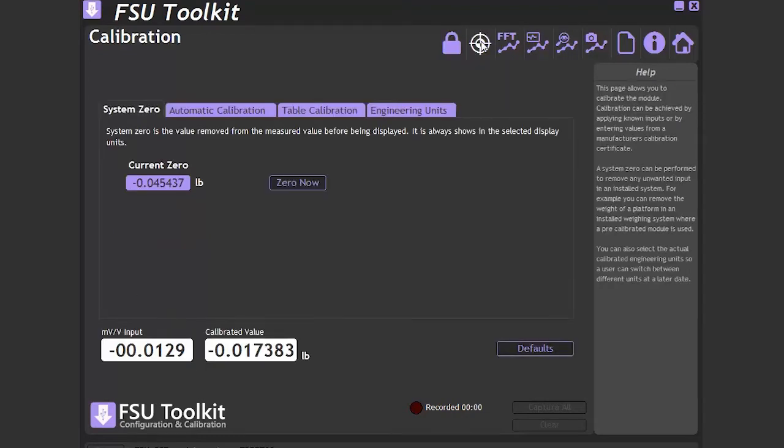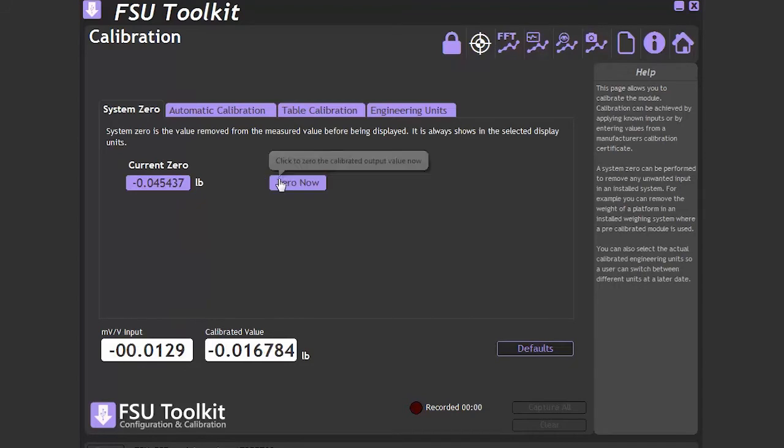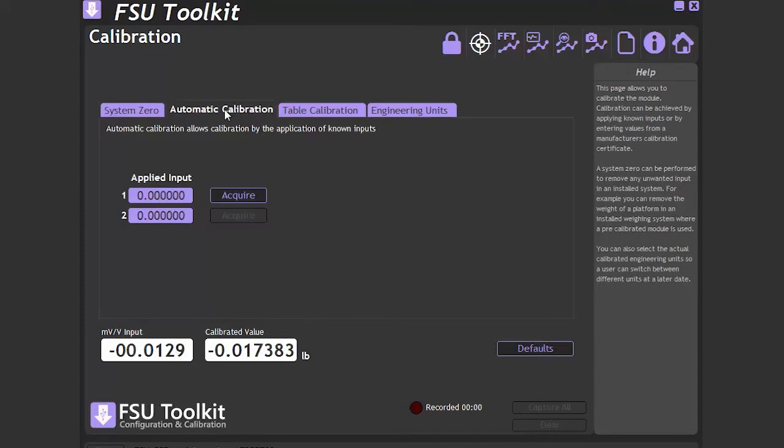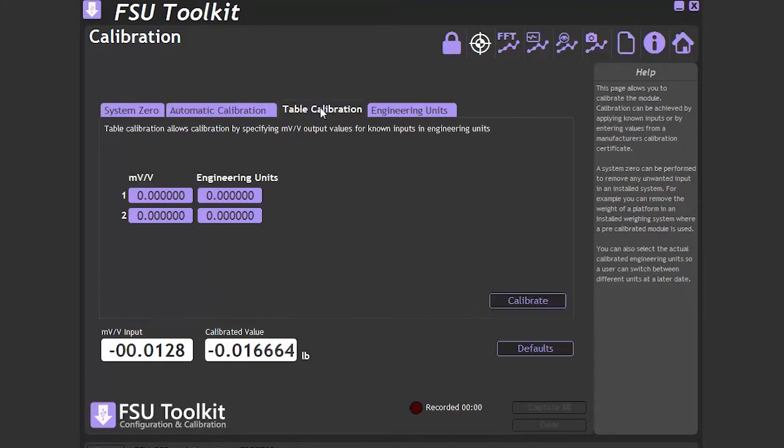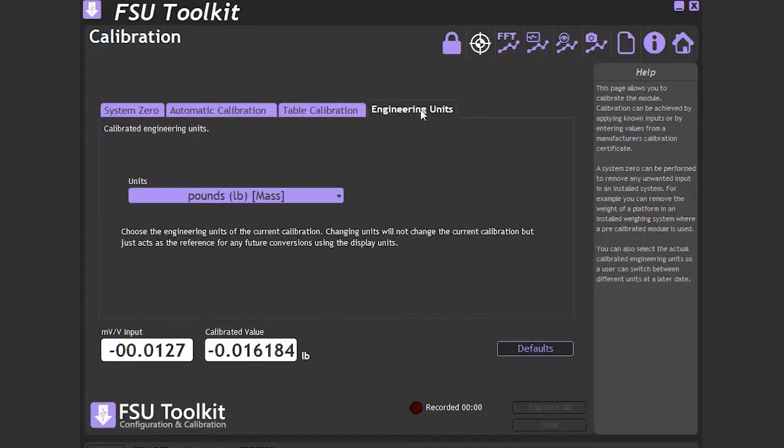And now, to the calibration page. Here, we can set the system 0, perform an automatic 2-point calibration with known weights, perform a 2-point table calibration using data from the calibration certificate, and set the calibrated engineering units.